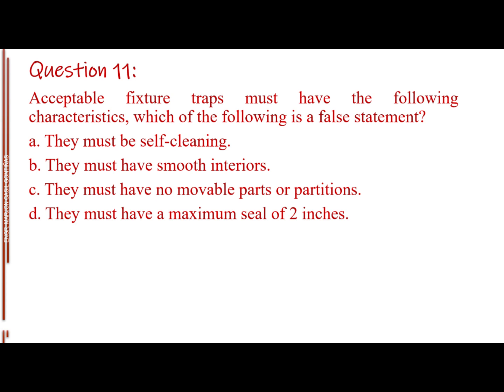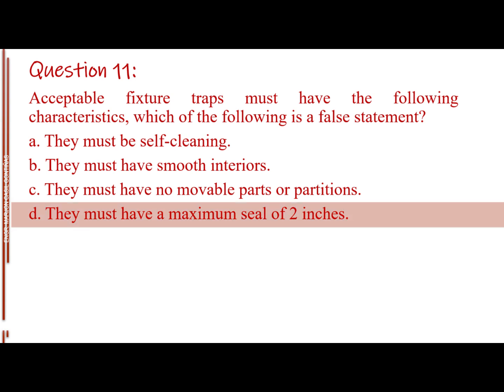Question number 11. Acceptable fixture traps must have the following characteristics — which of the following is a false statement? Letter A, they must be self-cleaning. Letter B, they must have smooth interiors. Letter C, they must have no movable parts or partitions. Letter D, they must have a maximum seal of 2 inches. The answer is Letter D — it should have a minimum seal of 2 inches.